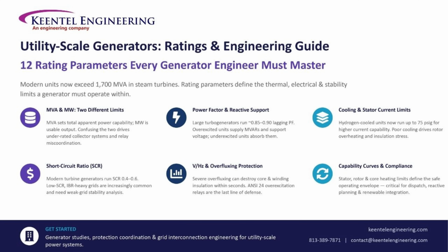So here's the bottom line on generator ratings. 12 parameters, from MVA and MW to power factor, cooling, short circuit ratio, and volts per hertz, define the real operating limits of every large generator on the grid. Get them wrong, and you're looking at overheating, insulation failure, or a protection trip you didn't see coming. Get them right, and you've got a machine that performs safely for decades. As generators push past 1700 megavolt amps and grids lean harder on inverter-based resources, understanding these ratings isn't optional anymore.